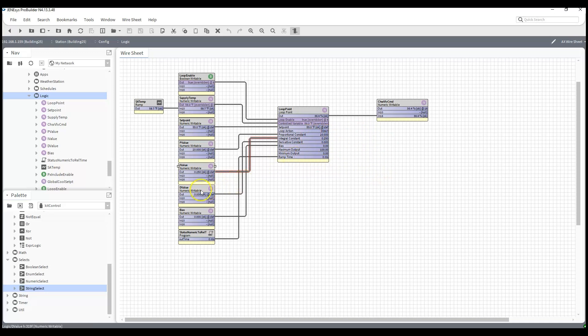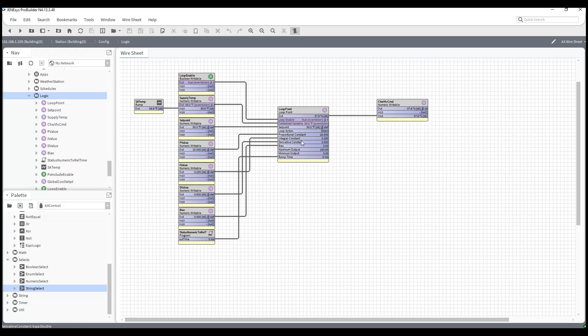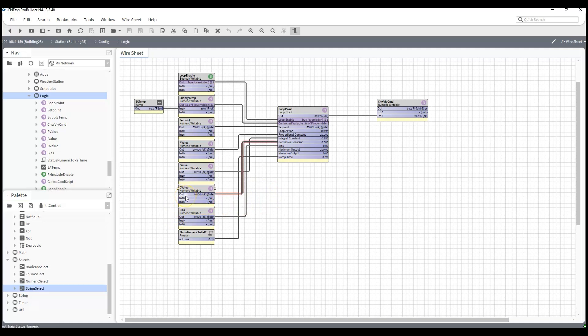Now as far as derivative, very few times where I do this. Some people will use it to maintain static pressure - I've never had to do that. The only time I've ever used a derivative, which counteracts the integral, is for like cascading boilers. There could be some other scenarios there, but I've only maybe used derivative like three times in my career. So normally this is probably not used in HVAC applications, at least for what we do. It can stay mostly ignored.